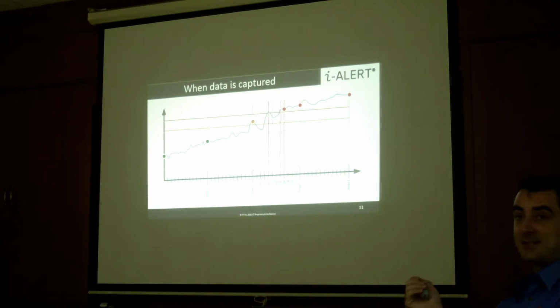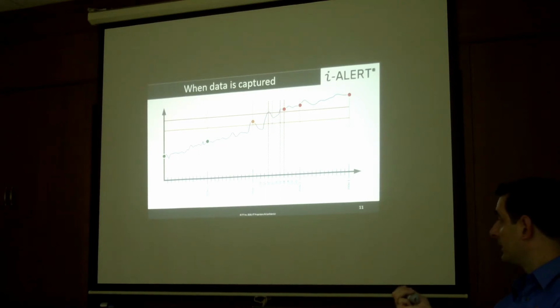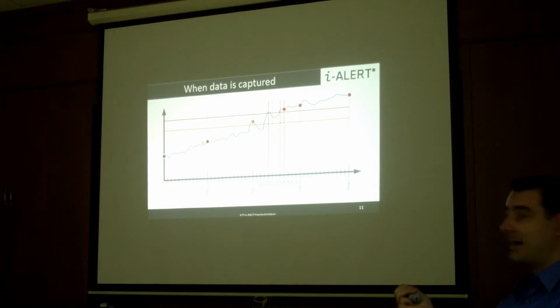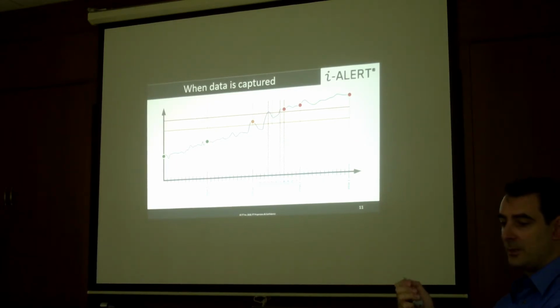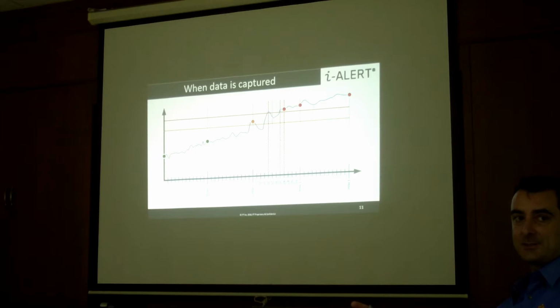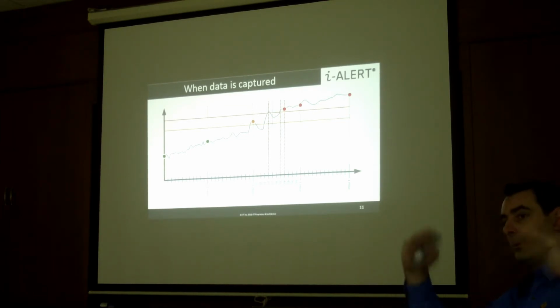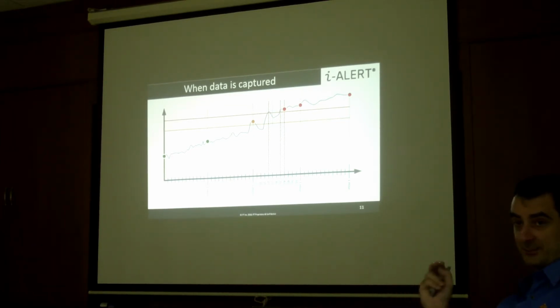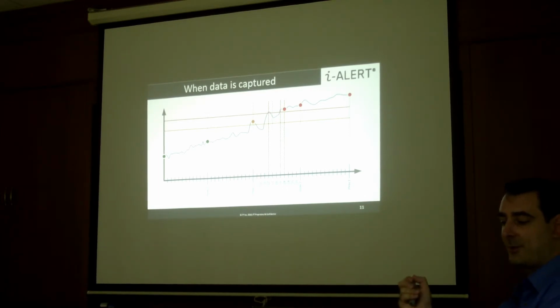So what this shows you is that the alarm levels are very important. If you had a value here, and your alarm level is very high, if the vibrations spike, you might not capture it. So for customers, like if I'm talking to a customer with a lot of sensors in the site, we recommend you let them run automatically for 30 days. And then after that, we lower all the alarms to be above the top of the trend. That way, if there's any sudden change, you capture it and you get the time waveform and you can try and identify what caused it.